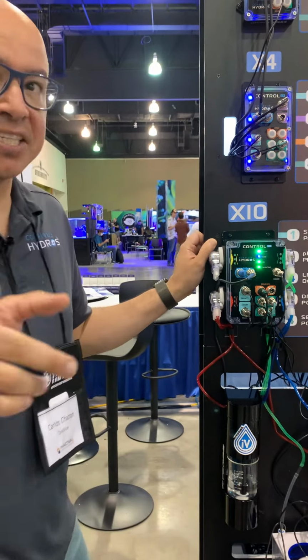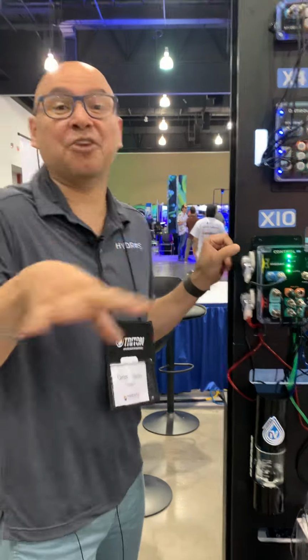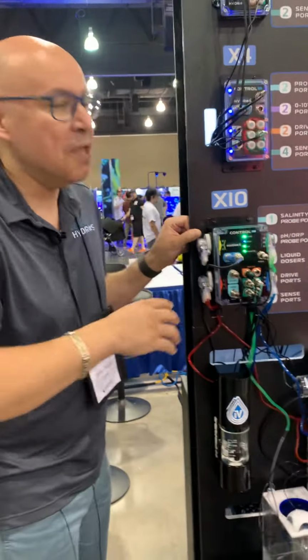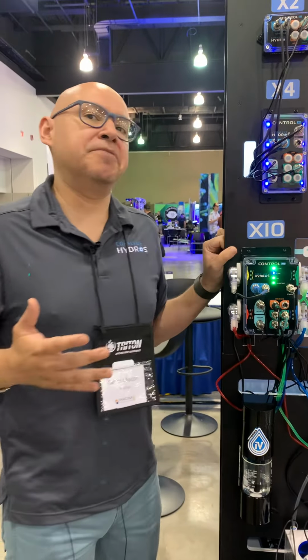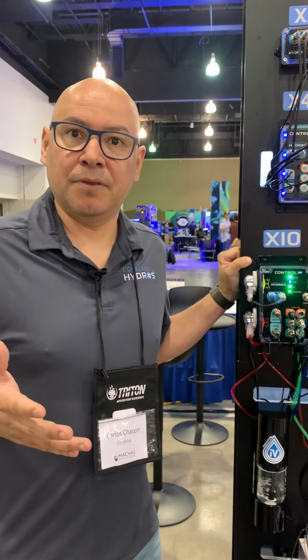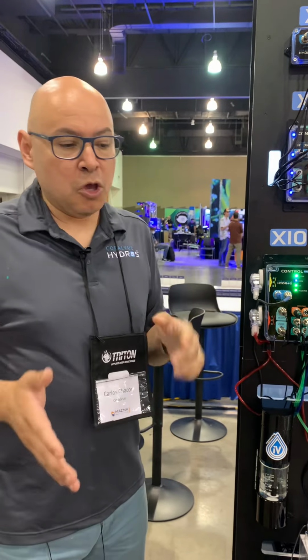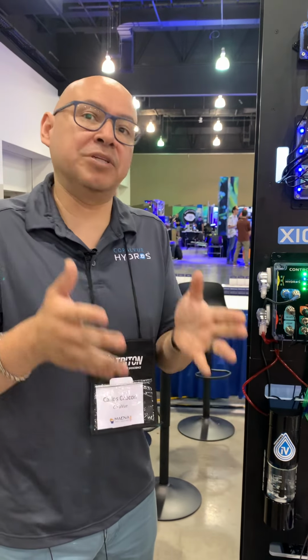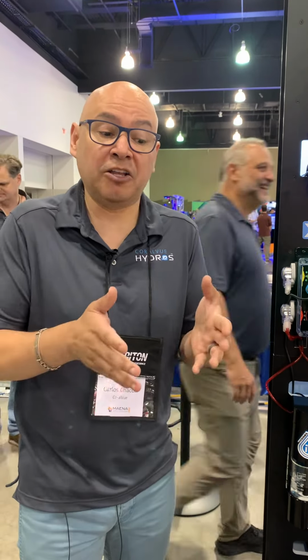And it doesn't stop there. This is for the technical people. Every conductivity probe is not equal. It's like anything in life: you use equipment that was designed for a particular environment. Conductivity probes are designed for different environments. You have conductivity probes that test fresh water, probes that test salt water, and probes that test sewage. So depending on the environment, you have to buy the correct probe.